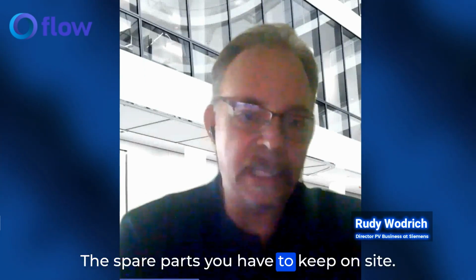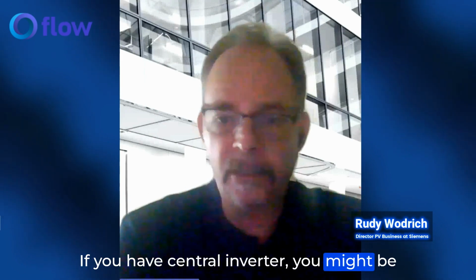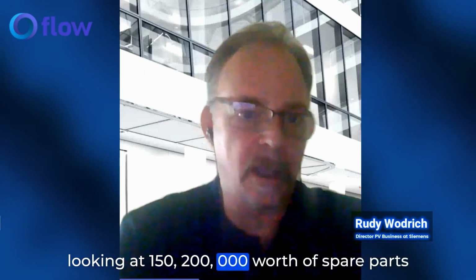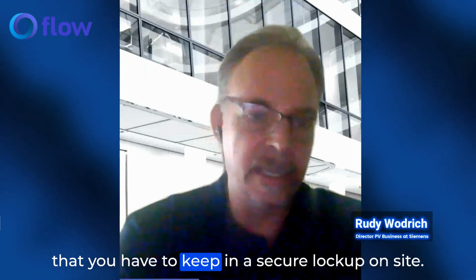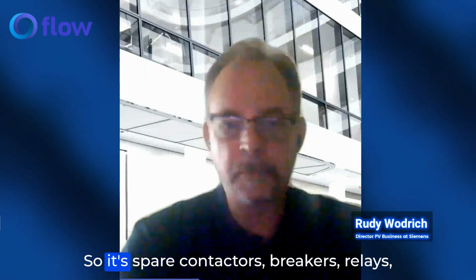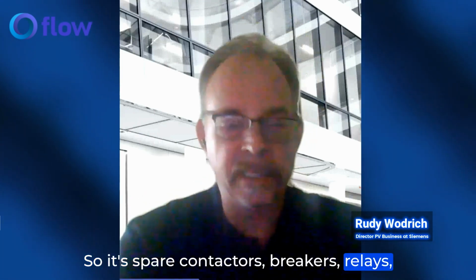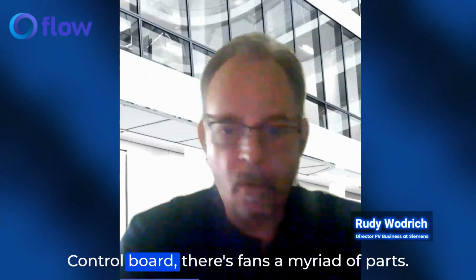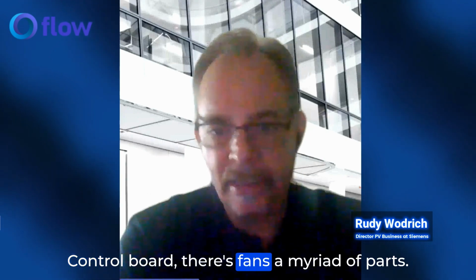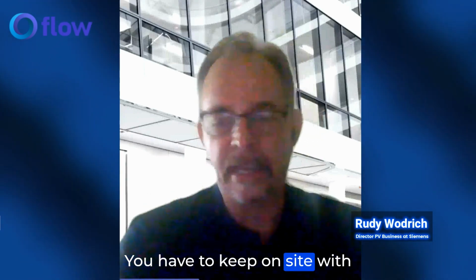The spare parts you have to keep on site. If you have central inverter, you might be looking at $150,000, $200,000 worth of spare parts that you have to keep in a secure lockup on site. So it's spare contactors, breakers, relays, IGBT stacks, IGBT devices, inductors, control board. There's fans, a myriad of parts you have to keep on site with a central.